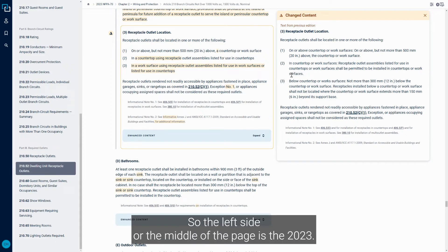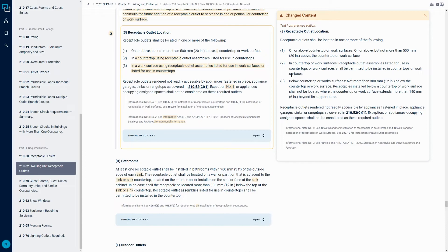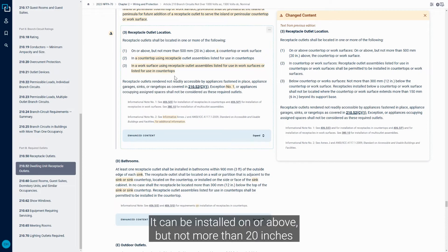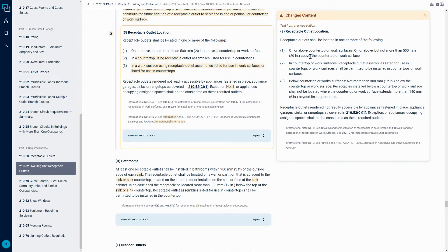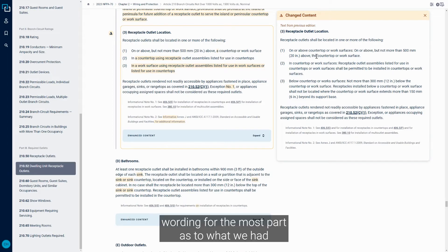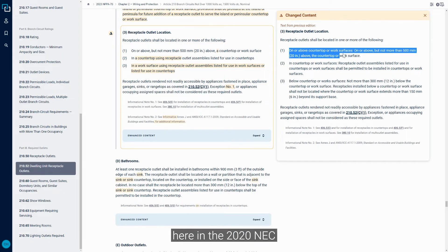So there's three different options, essentially, if we're going to install a Receptacle within an island or peninsula countertop or work surface that we can utilize. And I'm going to go back and forth a little between the 2023 and the 2020 here. So the left side or the middle of the page is the 2023. It can be installed on or above, but not more than 20 inches above the countertop or work surface, which is identical wording for the most part as to what we had here in the 2020 NEC.